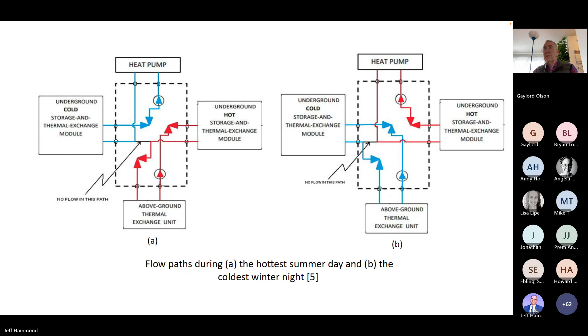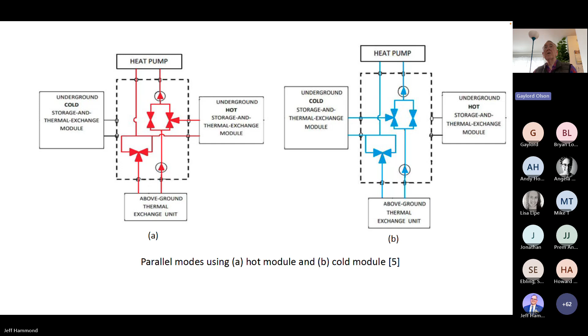So this shows what we're calling parallel mode. If you want, you can have some water coming from one of the ground loops and some other water coming from what we're calling here the above ground thermal exchange unit, dry cooler or solar thermal, whatever. You can have an equal flow from both of those blocks, and that's useful in the transition region between very cold and warmer. Go on to the next one.